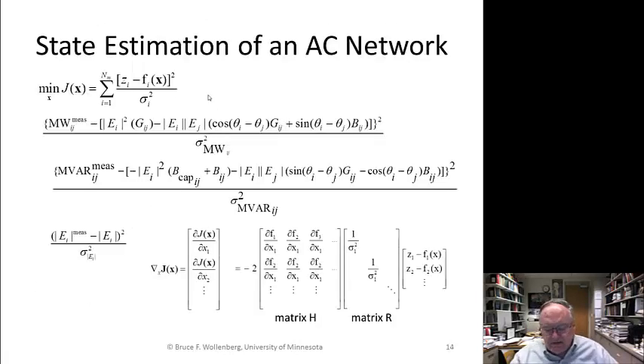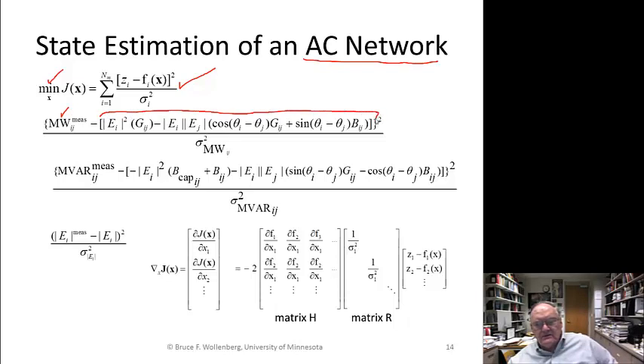Now, if I go to an AC network, well, then the minimum of J is the same function that we used before, except that where we have a megawatt measurement, we have this great big non-linear function. And I have that squared divided by the megawatt measurement sigma. And then I have the megavar minus another long equation. And I have that squared divided by sigma. And here it is for the voltage. It's just voltage magnitude minus magnitude over the sigma.